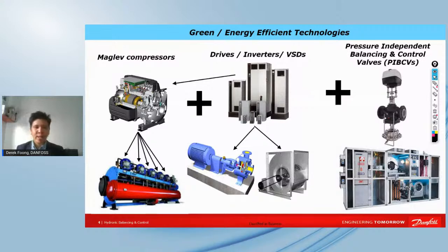In the middle, we also know that inverters are integrated into pumps and fans, and also permanent magnet electric fans are coming into the market. Singapore and Europe are also adopting these new technologies in inverters in the fan. On the right-hand side, we have what we call pressure independent balancing and control valves, in short PIBCVs, in air handling units or in fan coils. And if you're dealing with district cooling, we even have larger sizes.